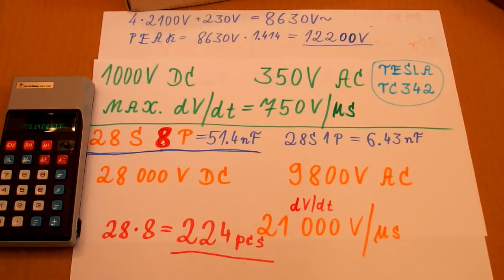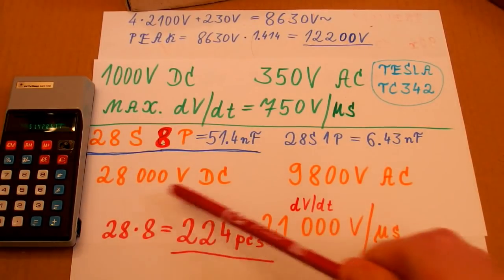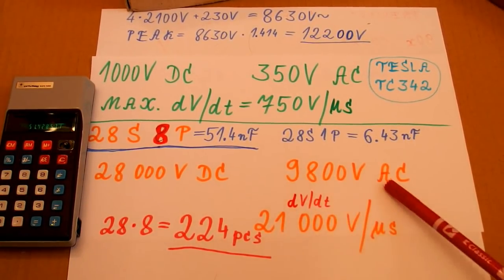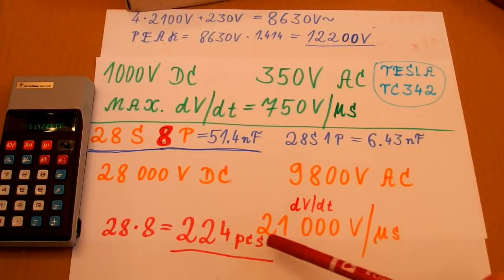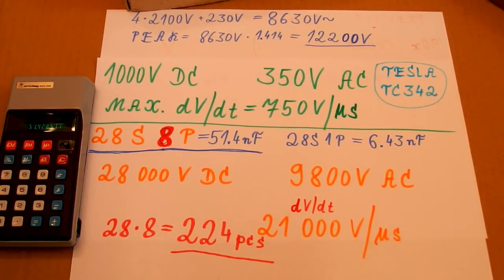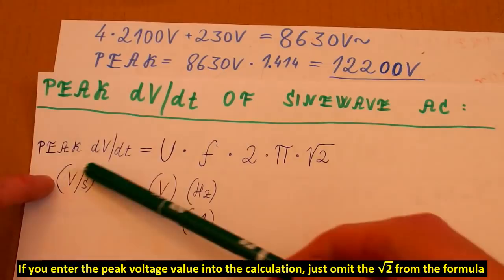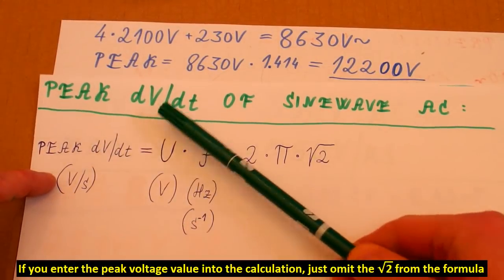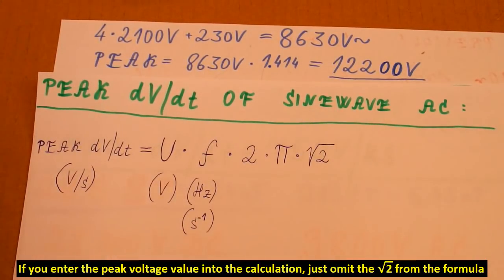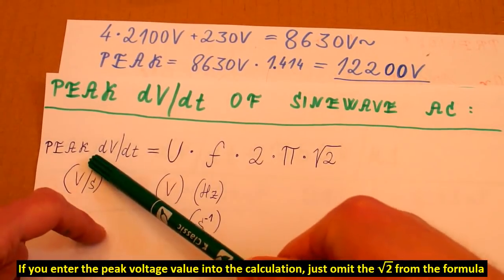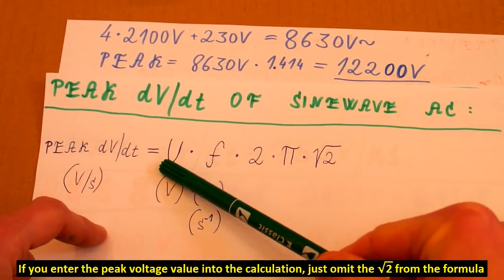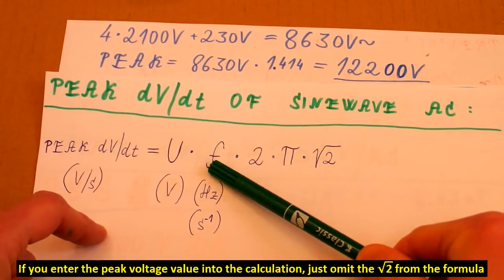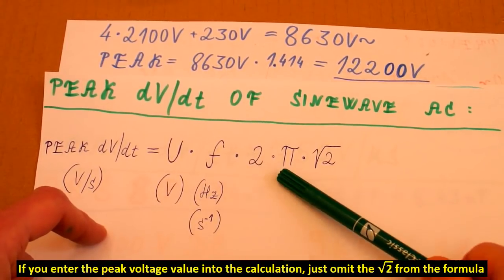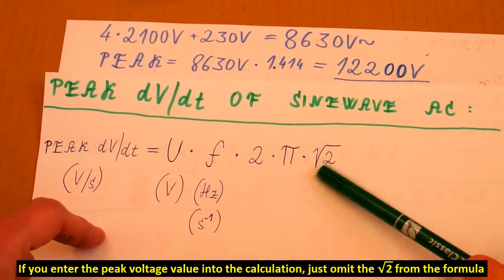So I've calculated my capacitor bank, and the DC voltage rating is fine, the AC voltage rating is fine, and now, is the dV/dt rating fine? So let's take a look at this calculation of the peak dV/dt of a sine wave AC voltage. The peak dV/dt is basically the voltage, the AC voltage, times the frequency, times 2, times pi, times the square root of 2.